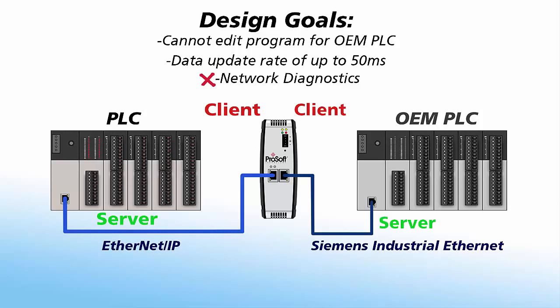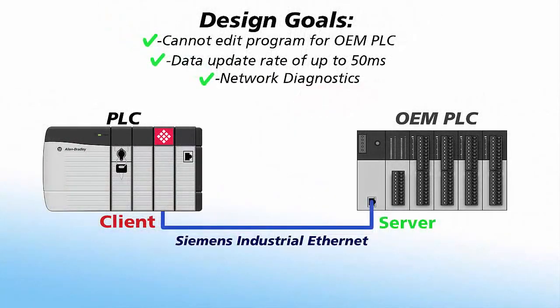The solution that meets all the application requirements would be to set up I/O messaging between the Ethernet IP PLC and our gateway. When PLCs do I/O messaging, sometimes called an I/O connection, they require a communication update interval to be set. This will ensure the communications between the PLC and gateway are fast and consistent, as they will be given priority over other communications. The PLC will also have access to communication diagnostic tags, which allow you to use your PLC programming software to troubleshoot problems.